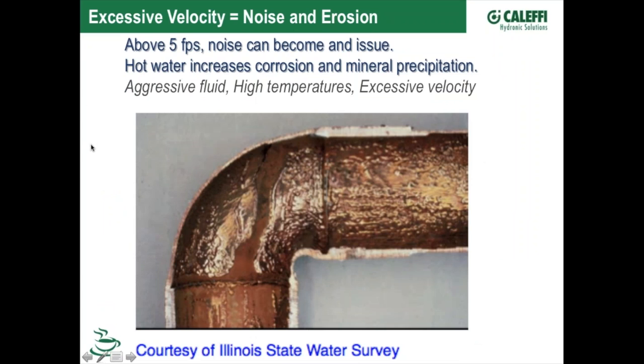And this is one of the things that can happen when you've got excessive velocity in piping. If we've used a piece of 3/4 pipe and we're running real high velocity through that, you'll actually start eroding the pipe. It's almost like somebody's taken an ice pick in here and chopped away at the copper. That's called corrosion erosion, and it can be caused by high velocity. The temperature of the water plays a part in this also. The hotter the water becomes, the more aggressive it can become.